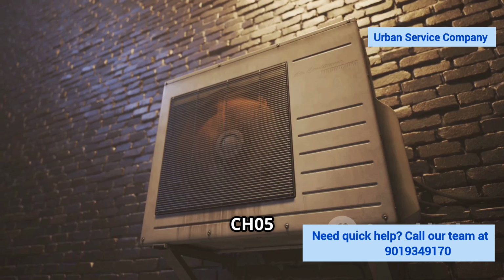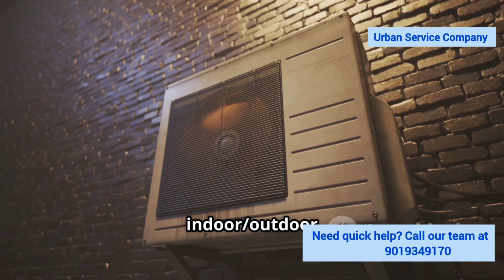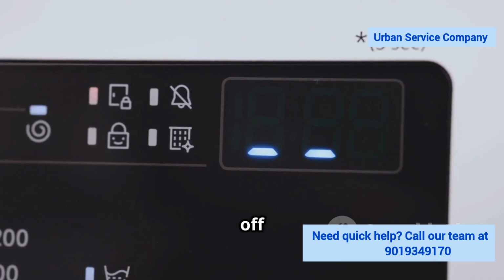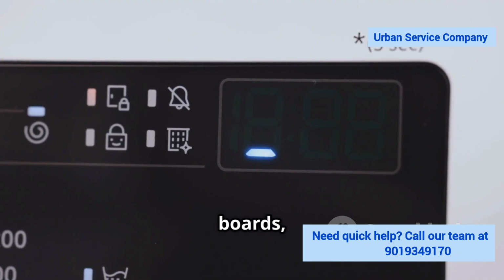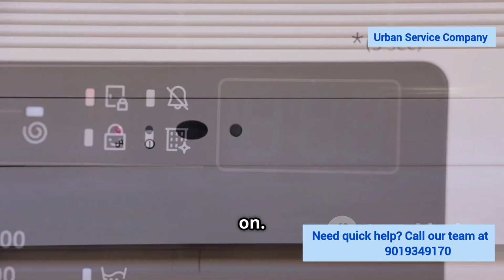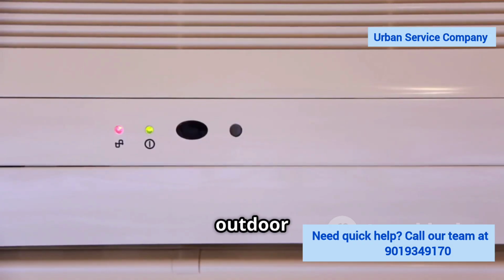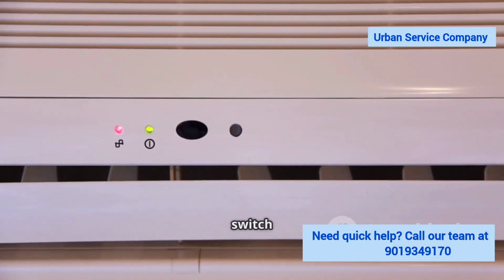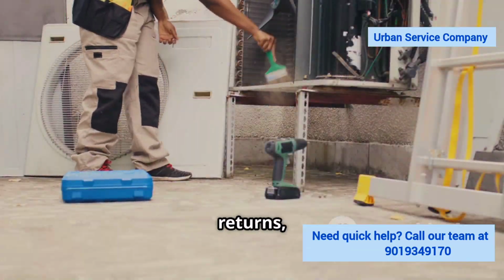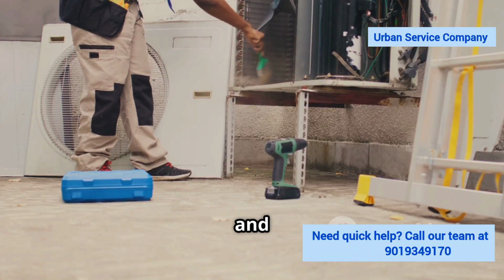Code CH05, indoor-outdoor communication error. Step 1. Flip the breaker off for 5 minutes to fully discharge the boards, then back on. Step 2. Make sure the outdoor unit has power and the service switch isn't off. Check any visible low-voltage cable for damage. Do not open panels. Step 3. If it returns, you need a tech to test the COM cable and boards.